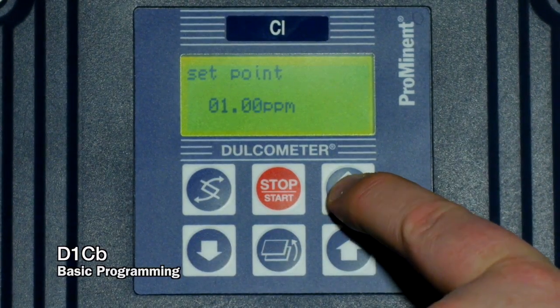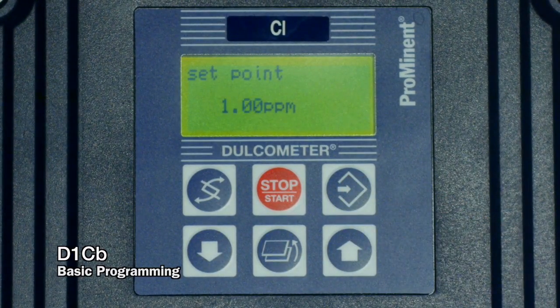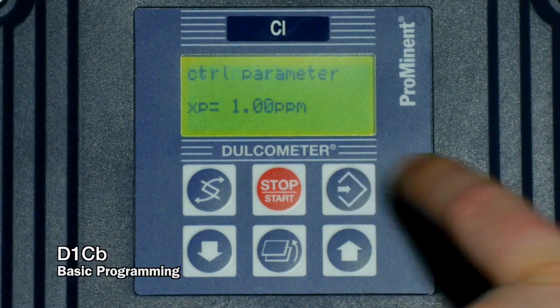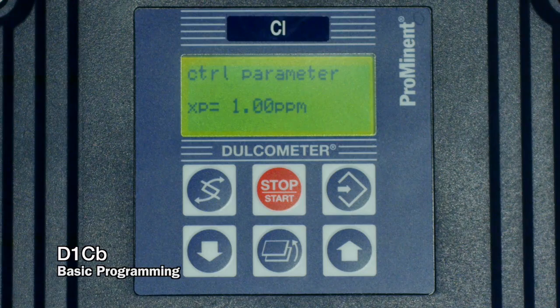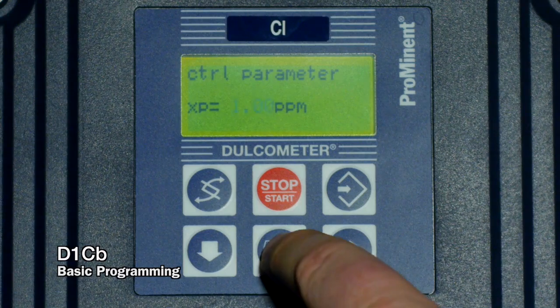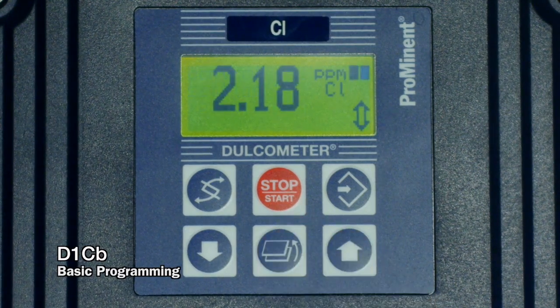When we're finished, we can hit enter. The complete whole number flashes again. Just to verify, we hit enter once again. Next it goes to our proportional setting. We're going to cover the PID settings in another video. You can hit the bottom center key twice to get back to the main display, and we're now set for a 1 part per million set point.